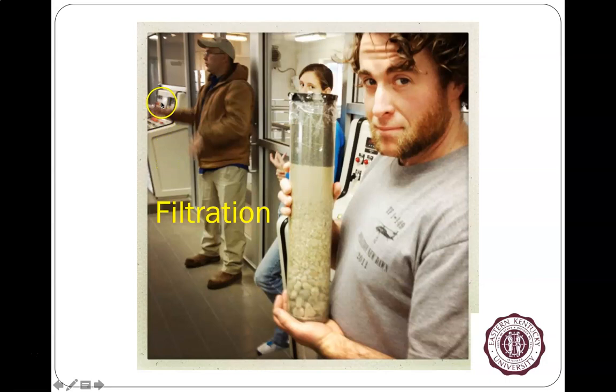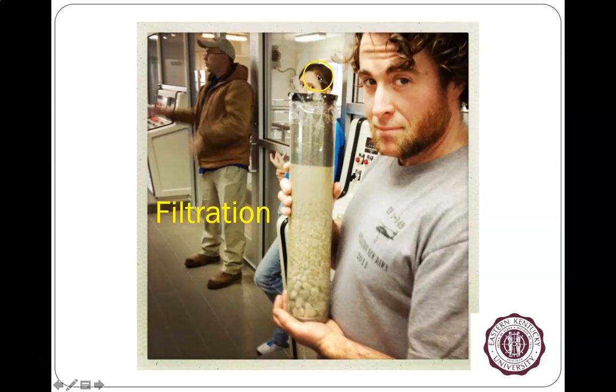Here is one of the instruments that monitors the amount of head pressure — the amount of weight of water that has to go on top of the filter to push it through. This tube shows you what a large rectangular bin looks like, and there are several of them behind these windows and more throughout the water plant. The water builds up on top, and the weight pushing it through is called the head pressure. The more head pressure required means potentially lower quality water coming out, so there's an optimal amount of head to maintain.